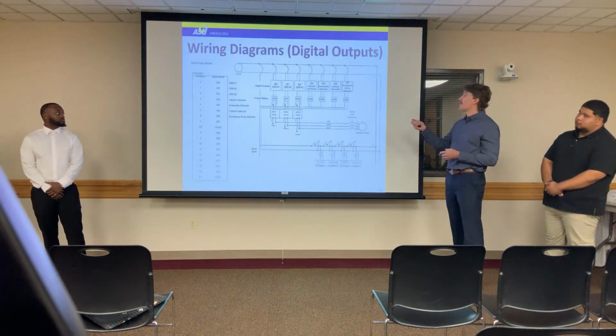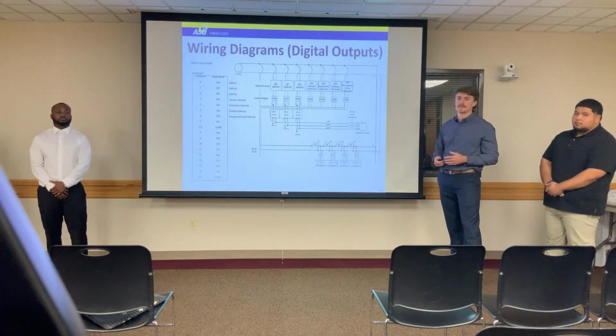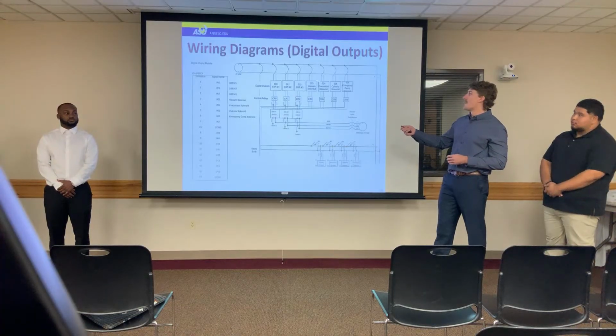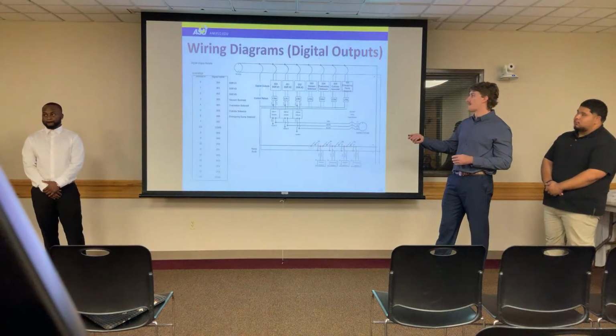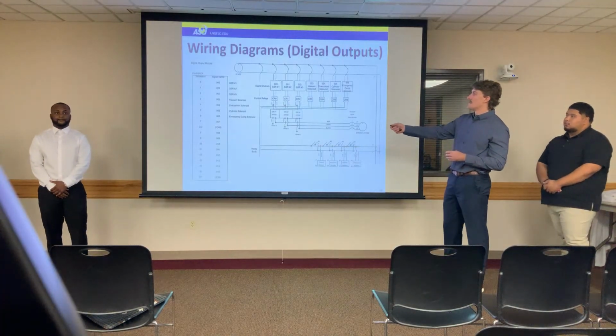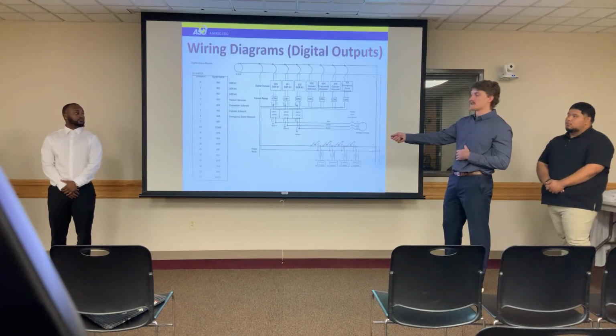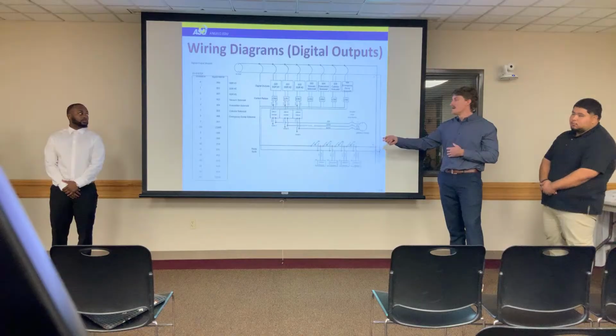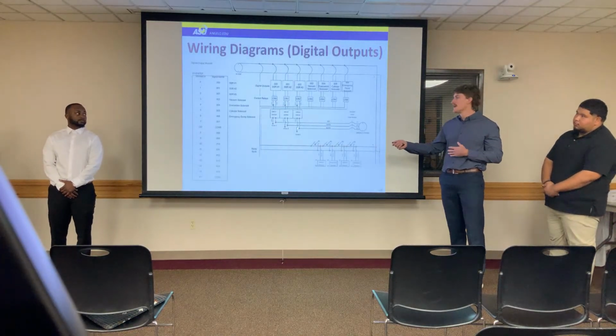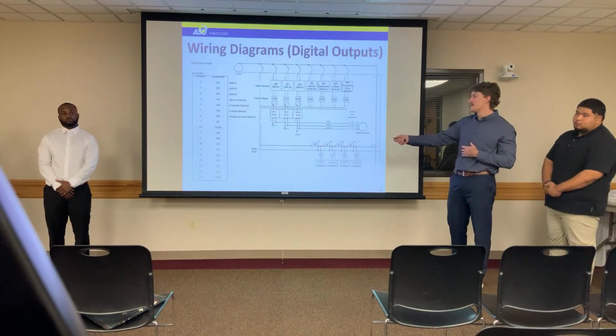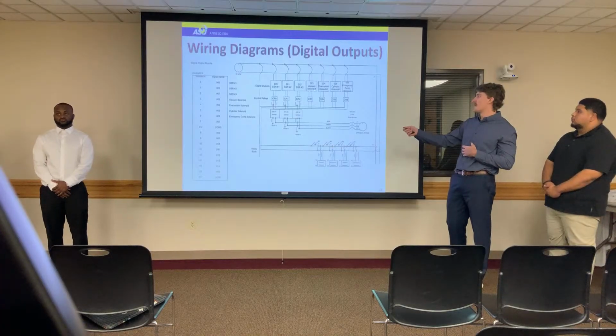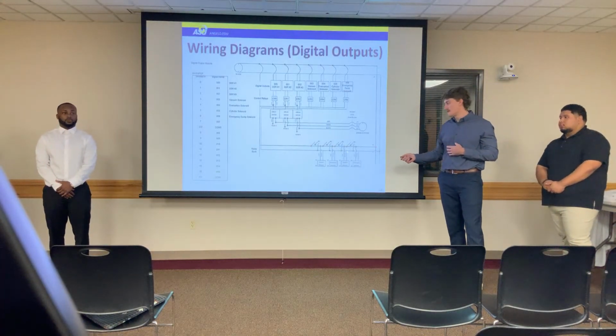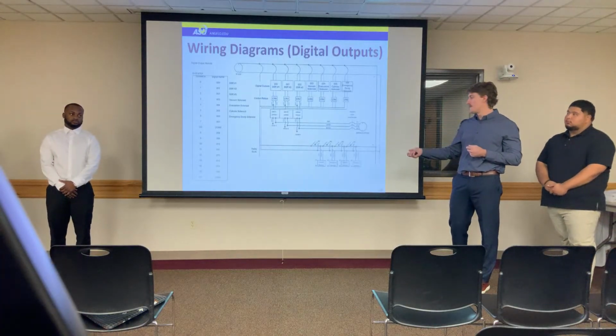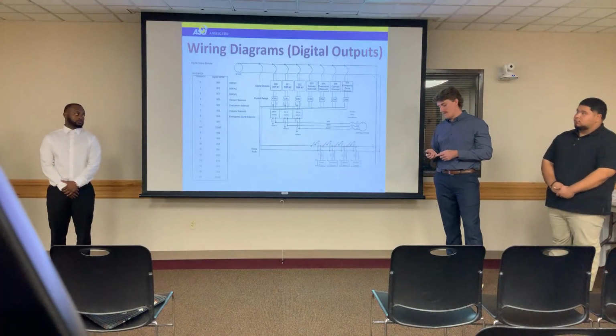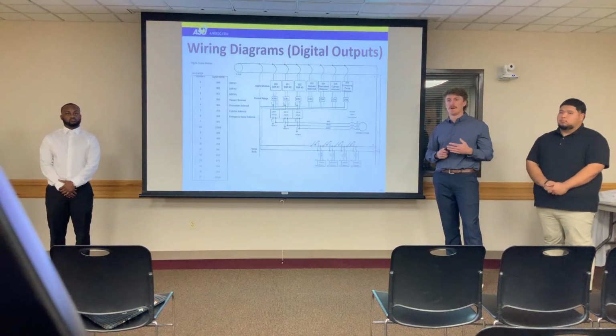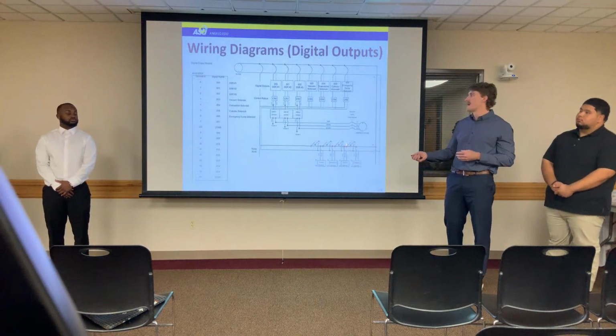Moving on, we needed the digital output module, which sends out the signals to turn on and off certain components in our machine. Starting from the top, moving left to right, we have all of these output signals coming from the module itself. The first three on the left are signals to our solid state relays, which run on 240 volts AC. The 24 volt signal switches those on and off like a light, and powers the heaters on and off if need be. At the bottom, we have our solenoids, where the signal comes in and turns them on and off if need be. The relay bank that we are running the solenoids off of supplies the actual power to run these components, rather than the module itself.